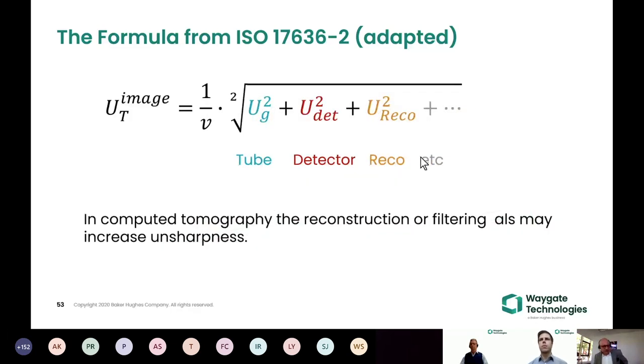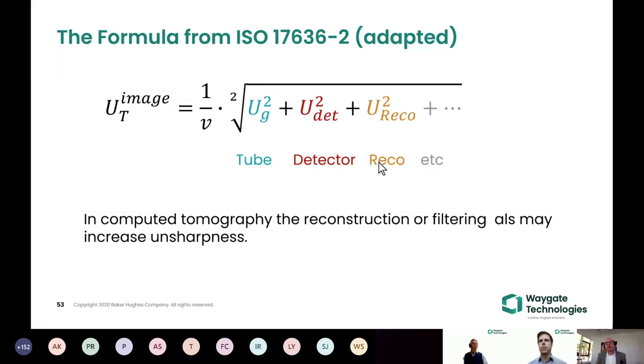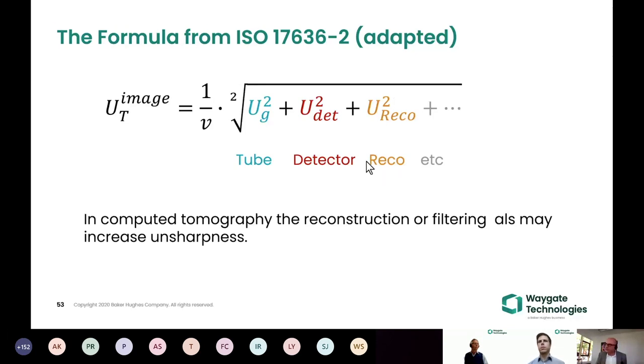Another important point: if you use a reconstruction algorithm not delivered with the system, be aware it can cause significant additional unsharpness. Reconstruction algorithms have internal filters which can degrade sharpness - I've found up to 40% additional unsharpness using algorithms obtained from outside sources. If you change the reconstruction algorithm in CT, you should always check whether it affects sharpness, as the effect can be quite remarkable and not just minor.